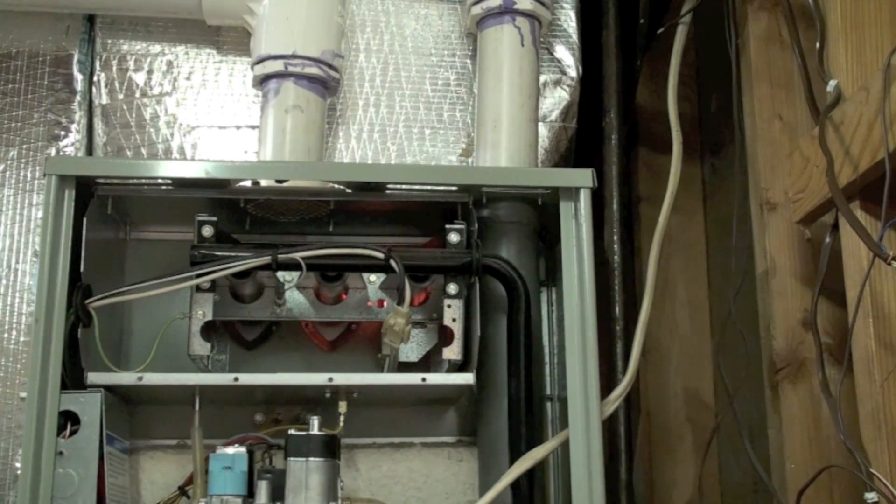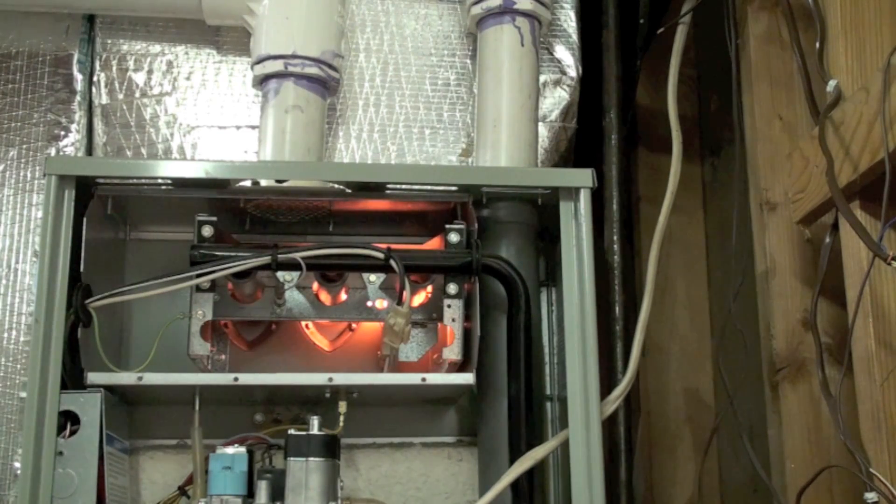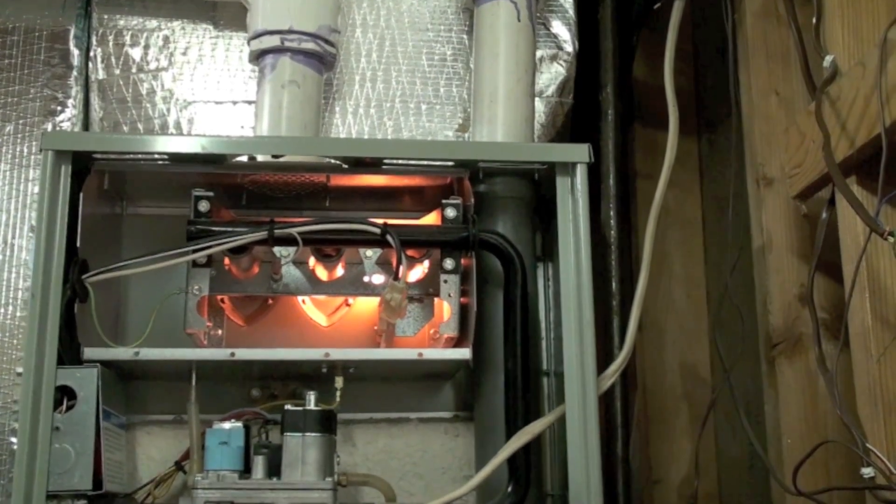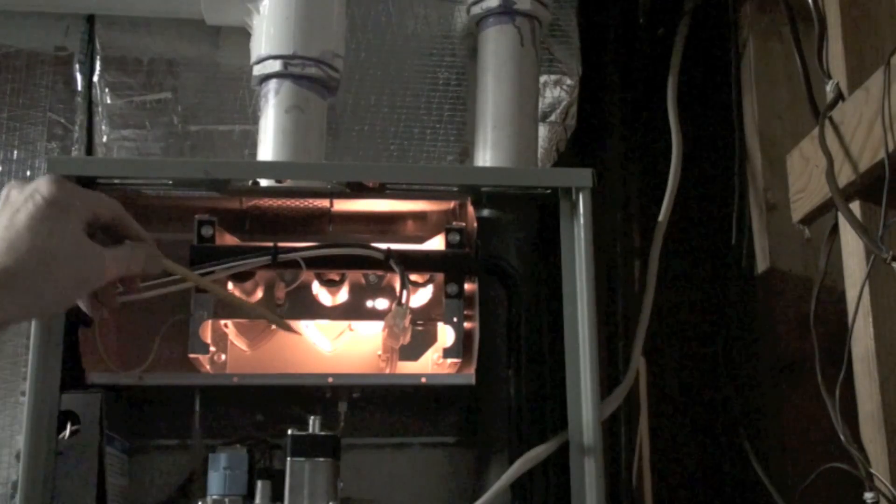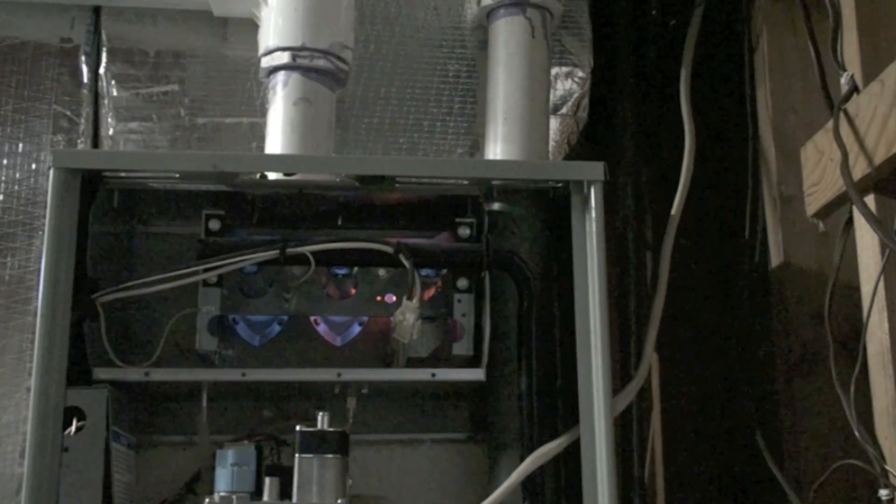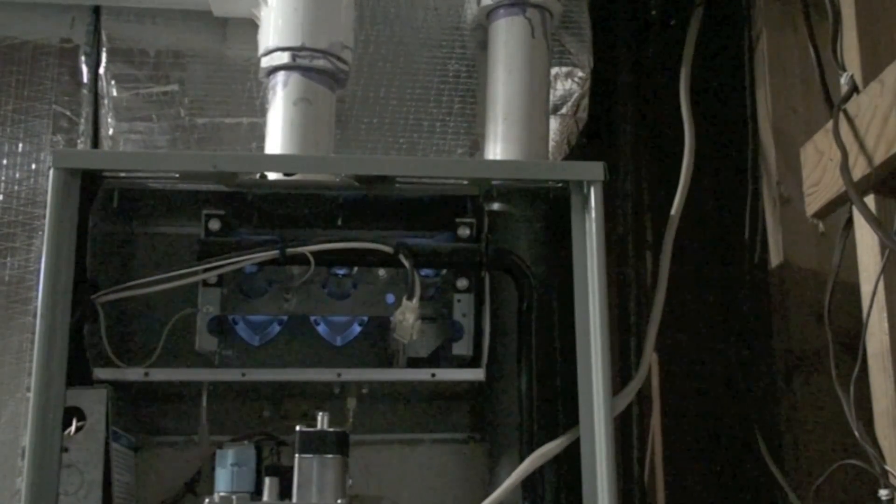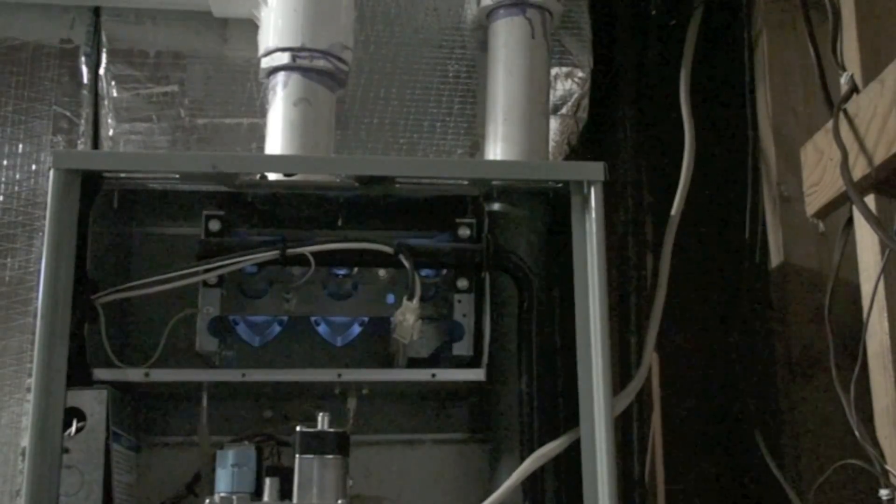Okay, this video is on the flame sensing rod. I've just fired this furnace up. The hot surface igniter is right here, that's the glow stick. These are the burners, there's three of them. Right here is the flame sense rod. Now the flame sense rod is nothing but a piece of stainless steel, there's nothing special about it. It doesn't perform any function other than conduct electricity.